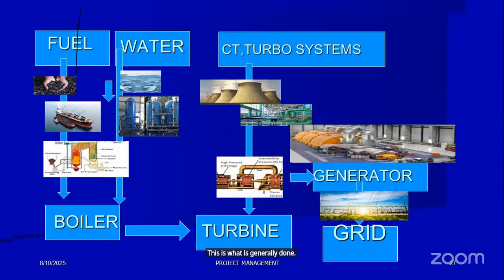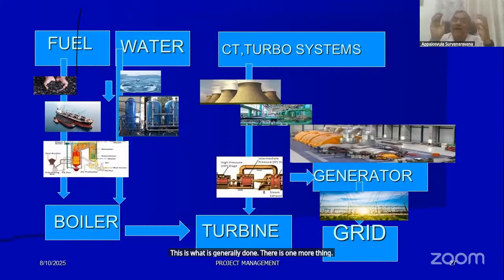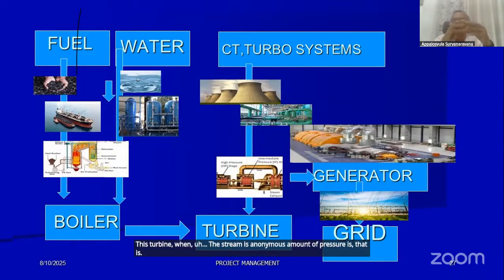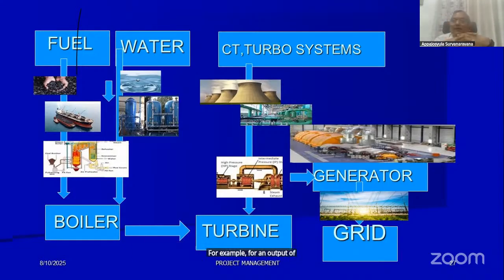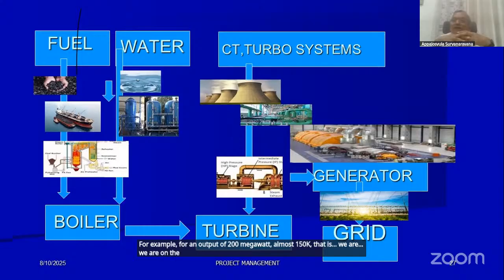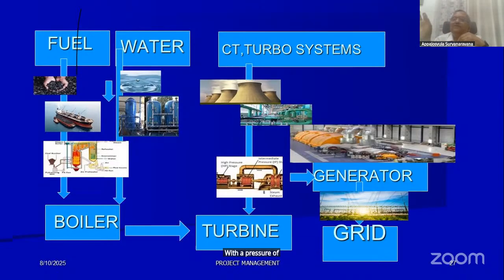There is one more thing. In this turbine, the steam has an enormous amount of pressure. For example, for an output of 200 megawatt, almost 150 kSc. On the ground we have a pressure of 1.033 kg per cm square, one atmospheric pressure. So for 200 megawatt generation, the steam is generated at a level of 620 tons per hour at a pressure of around 160 bar, 160 times the pressure on the ground.